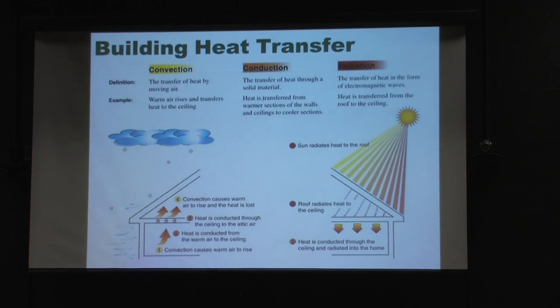This slide kind of oversimplifies what's going on in your building, because it's only showing the natural effects from the outdoors. It's not showing any internal loads. So along with the outdoors, we also have internal loads—people, lighting, and equipment—which, when turned on, all that power you're using goes to heat energy. Your cooling system has to pull that heat out and get rid of it to keep your space comfortable. All of that has to be accounted for.